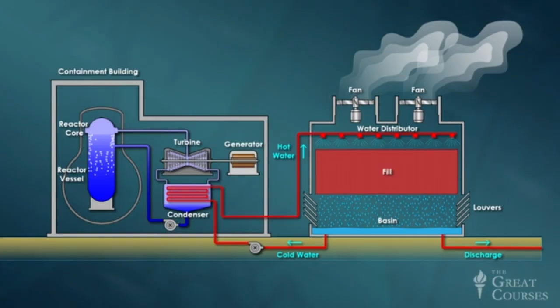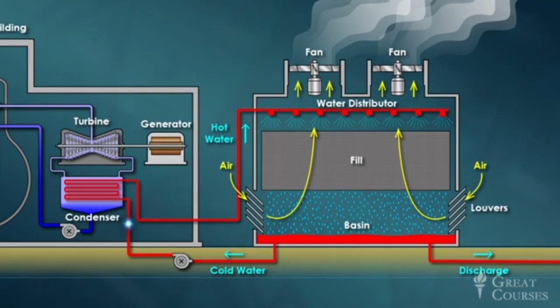At the same time, huge fans mounted at the top of the tower draw fresh air inward through louvers in the walls, through the fill, and then out through the roof. The moving air evaporates some of the water trickling down through the fill, and evaporation cools the remaining water back to its normal temperature by the time it reaches this basin at the bottom of the tower. Some of this cooled water is discharged back into the river to prevent the concentration of dissolved minerals from getting too high. Fresh water from the river is then added to replace the losses from both discharge and evaporation, and then the cooled water is recirculated back to the condenser.